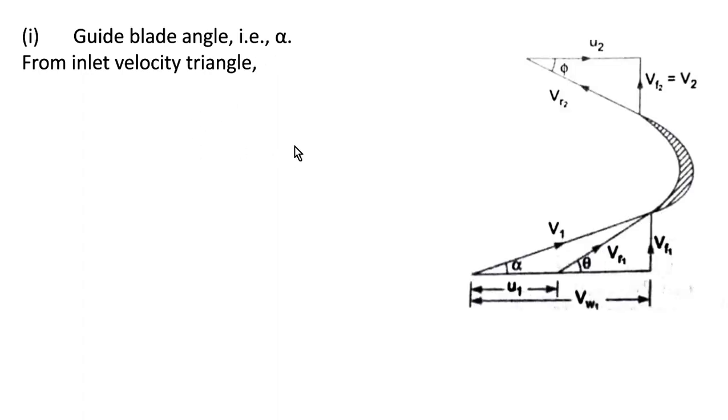First we need to find the guide blade angle, that is α. For that, we take the inlet velocity triangle from the given figure. tan α = vf₁/vw₁. Since we know the values of vf₁ and vw₁, substituting gives us 0.66.